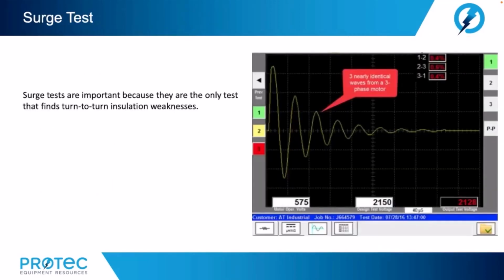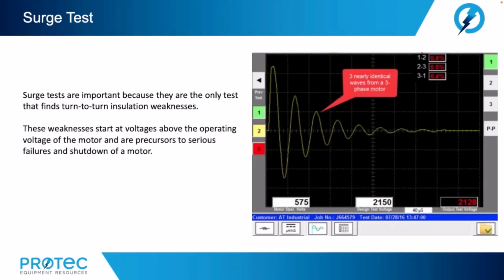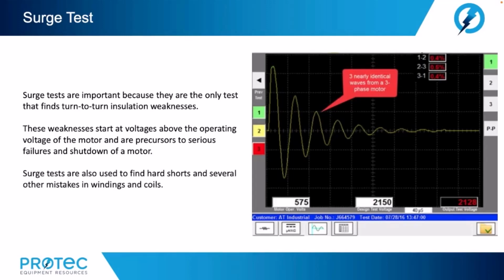And let's move away now from high potential testing and let's look at the surge test. Surge tests are important because they are the only tests that find turn-to-turn insulation weaknesses. These weaknesses start at voltages above the operating voltage of the motor and are precursors to serious failures and shutdown of a motor. Surge tests are also used to find hard shorts and several other mistakes in windings and coils.